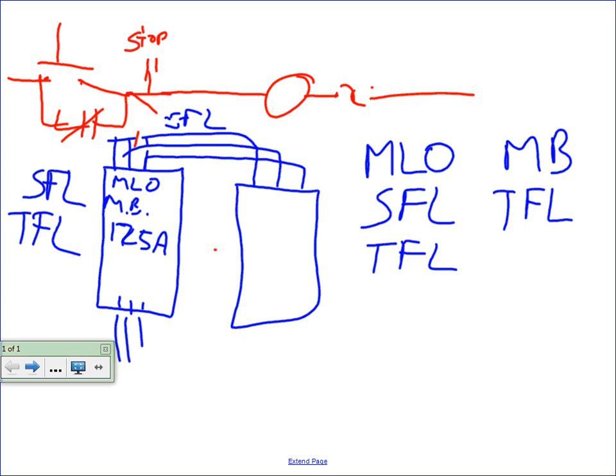which is on page 9-20 or 9-21, sorry. And that's called our I-Line panel or power distribution panel. Okay, you can use that at 208 or 480 volt, but it would normally be the main service type panel for your building. This panel can handle up to like 1200 amp branch mounted breakers, all the way down to 15 amp, and anything in between. So if you've got a panelboard that requires quite a few larger capacity breakers, you will probably be looking at an I-Line panel as a service panel.